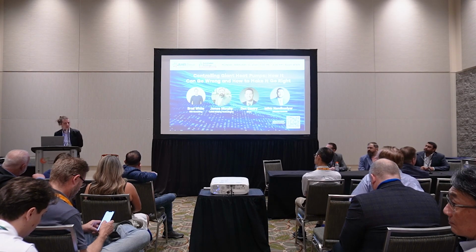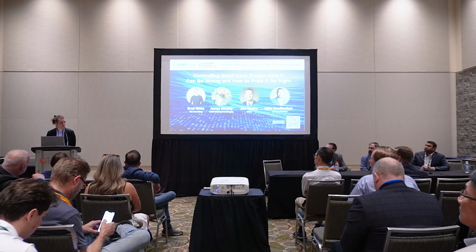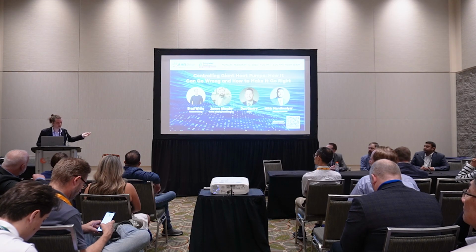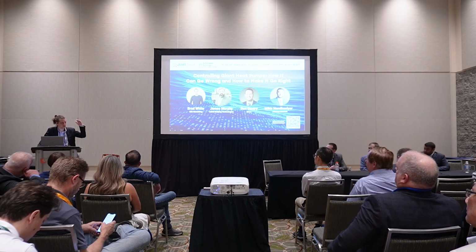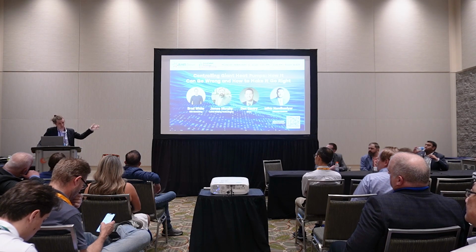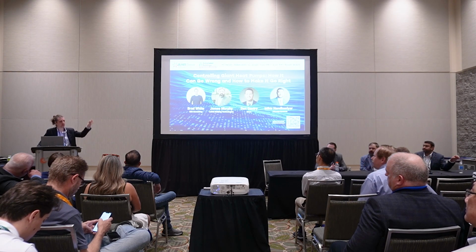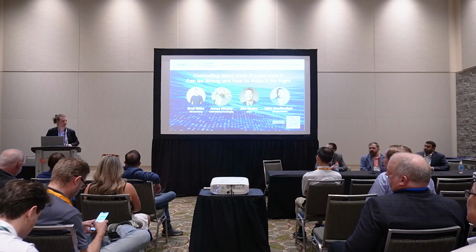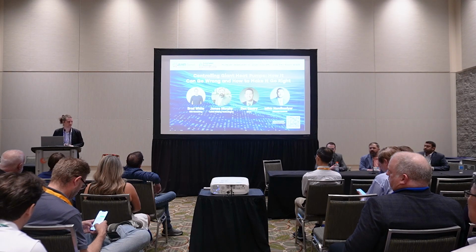We're doing high level feasibility studies. Our rule of thumb is, if we're doing a retrofit, I usually say to size a heat pump to 50-60% of the peak load. So let's say your design load is at whatever temperature, 0 or 17 Fahrenheit, wherever you are. 50-60% of that is what my heat pump is designed for, and then I assume any hours beyond that are going to be my backup source. But that usually covers like 80% of the energy use, because there are so few hours spent there. If you're trying to optimize the cost benefit of your system, that's where we found the sweet spot to be. It's very expensive to do a full heating load with a heat pump, and we rarely do it.